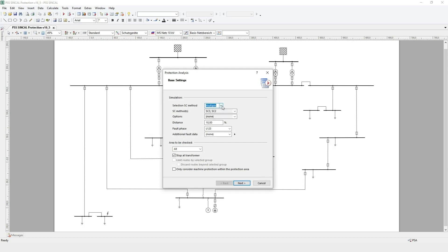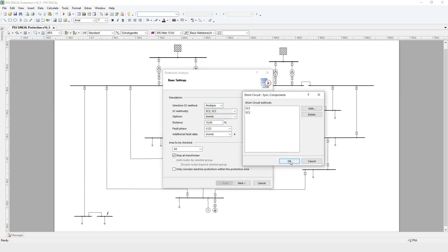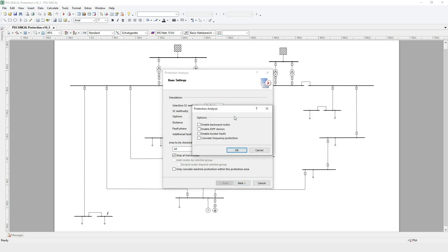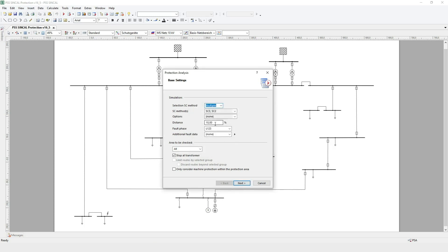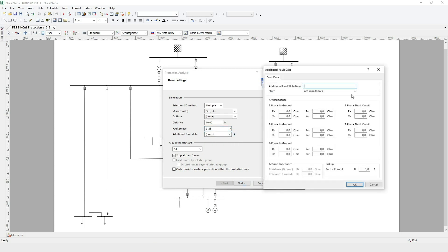Here you see the base settings. You can decide which fault types you want to analyze, and choose to consider differential and frequency protection, and whether to include busbar faults. In the distance field, set the step size to define how many fault events should be calculated along a protection area. The fault phase setting defines the faulty phases, which is especially interesting for unbalanced networks. The additional fault data is used to set arc and ground impedances.